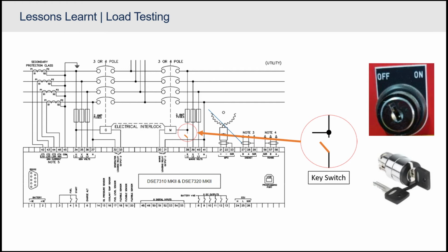For that reason, we implement a key switch where we simulate a power failure and test the whole system. As soon as you simulate the power failure by switching that key switch, it shows a phase dropping, and the switchgear picks that up and transfers the load from mains to the generator. The generator would have started up by then and takes full load as if there were a power outage. That's actually a very easy way to do proper load testing on a generator.